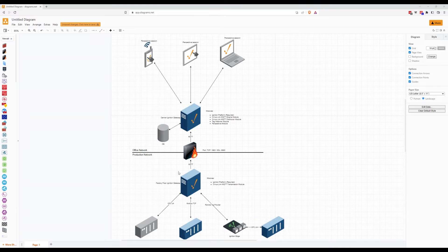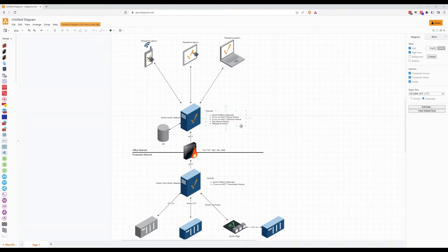We have our factory floor Ignition gateway. On this gateway we have the modules: the Ignition platform module, which is always required, and then we have the Sepasoft MQTT Transmission module connected there as well. All the tags we're creating on this Ignition gateway we are publishing through MQTT up to the central Ignition gateway, which has the Ignition platform module, the Sepasoft MQTT Distributor module, the tag history module, and the Perspective module.